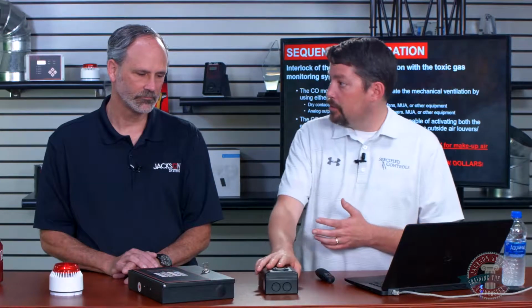The CO monitoring system shall activate the mechanical ventilation by using either dry contacts to operate the dampers, louvers, fans, whatever it might be, or analog outputs to modulate. So either we're going to bring them all on, or we're going to modulate those various pieces. And it's done in multiple ways, but through a panel in most cases. Also, the sensor itself can do this if it's a small application. But we will determine the best way to do this. Usually the engineer will tell us, but oftentimes it's a design build, and we'll offer up the suggestion.